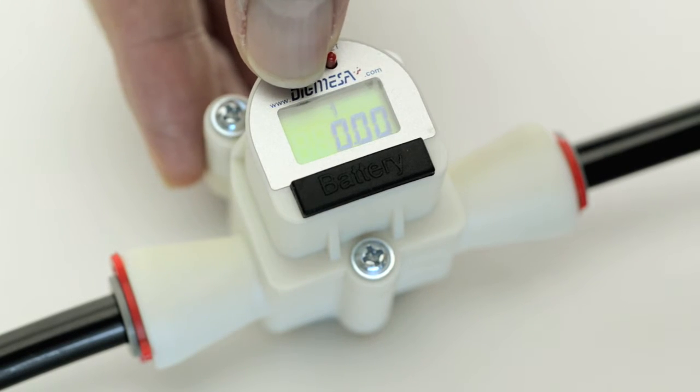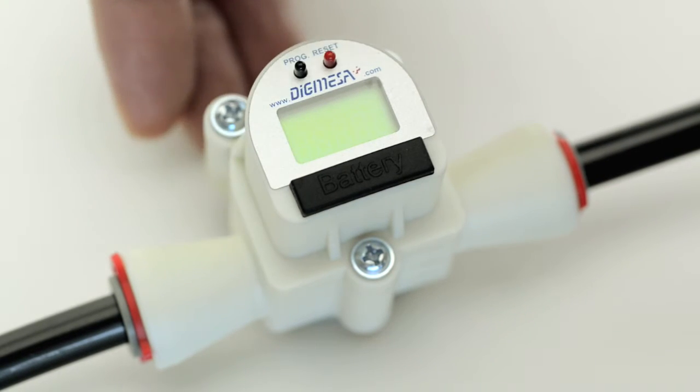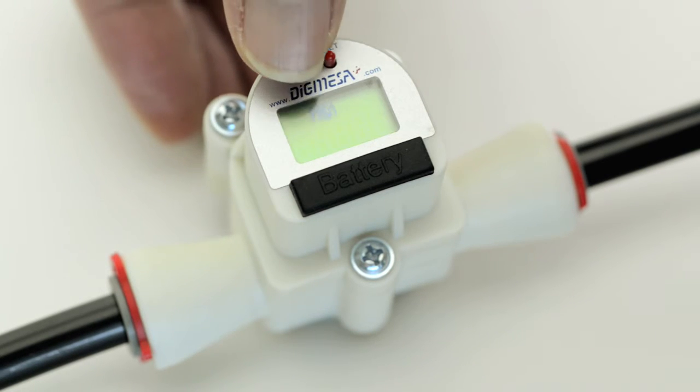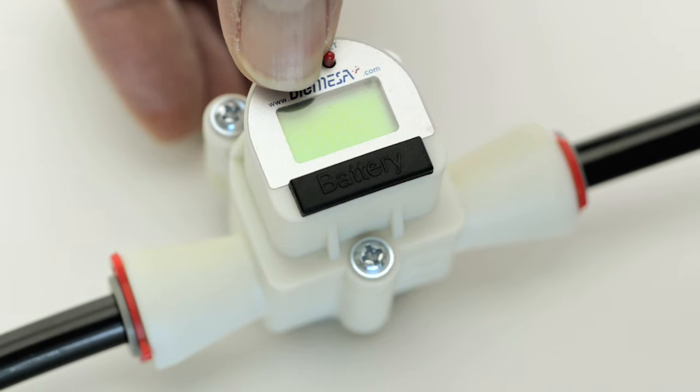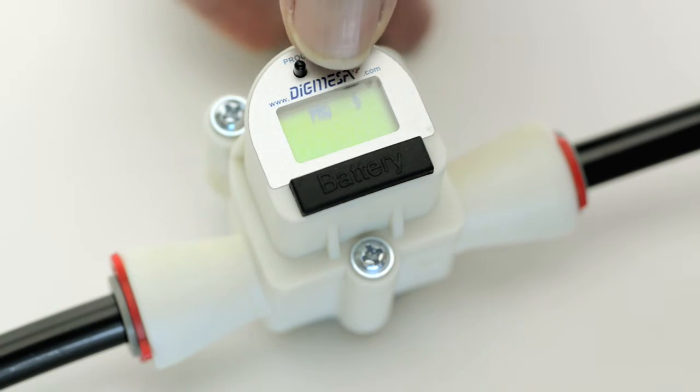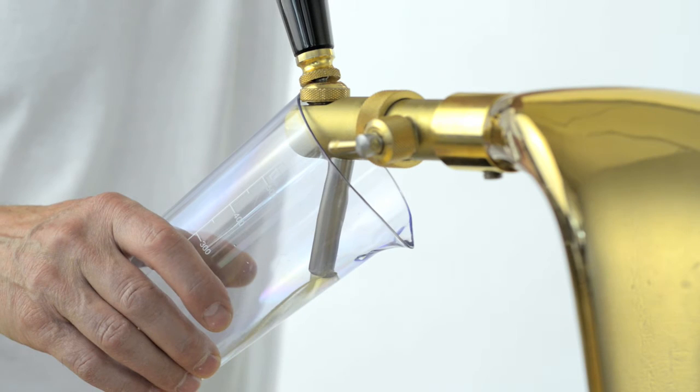Hold the black program pin down until the message PRG flashes on the display, then release it. Now press the black program pin five times in a row until the message PRG5 flashes on the display. Now press the red reset pin once. A hyphen appears on the right. The flow sensor is now ready for automatic calibration.